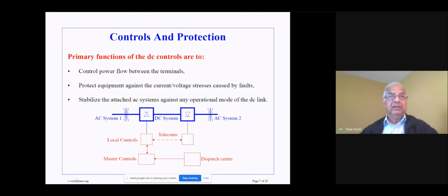And finally, the controls must also stabilize the attached AC systems against any operational mode of the DC link. So in here we show a two-terminal HVDC system. There could be a transmission line or could not be a transmission line, i.e. this could be a back-to-back connection, connecting two AC systems, AC system 1 with AC system 2. In red over here, we see the controls.